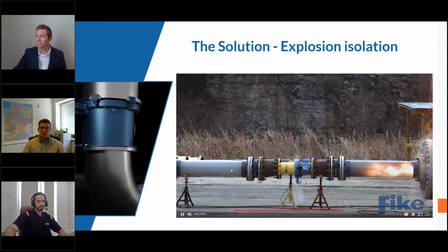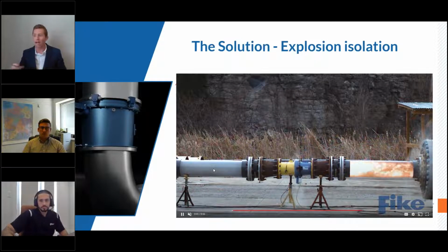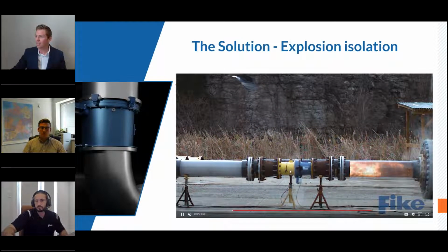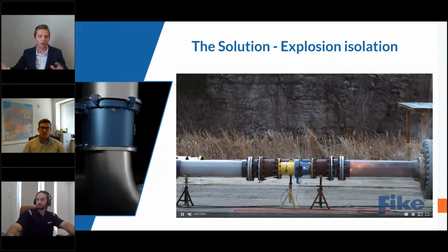And you can also see pressure oscillations trying to jam it open, pull it back open. So it locks in place. This can be put vertically. It can be put on however many bins you want. And look, it's isolated the explosion. Here's all that fuel just sitting over here, not ignited. That's how you know it works. Pretty cool.